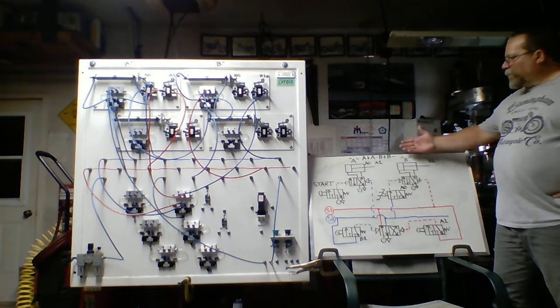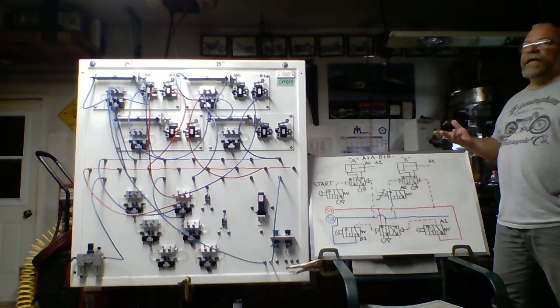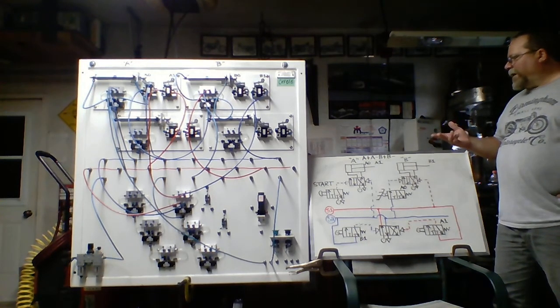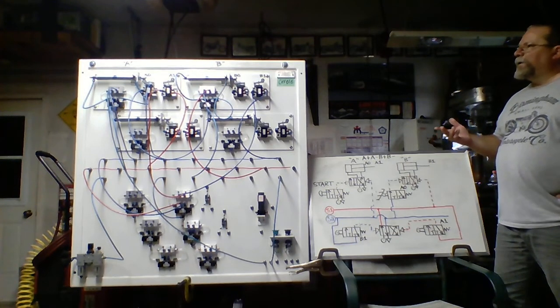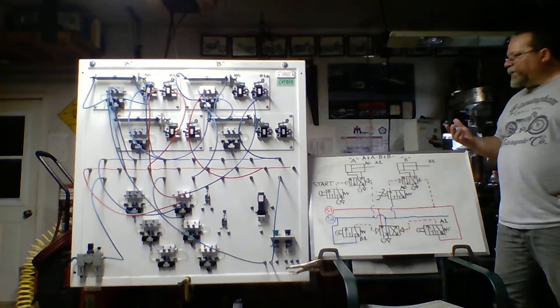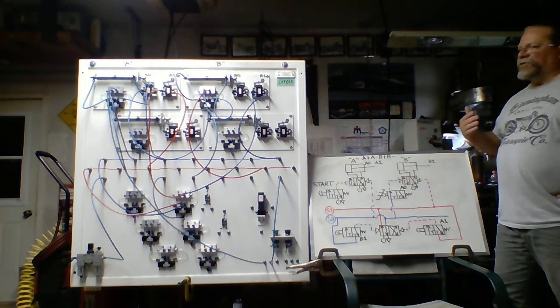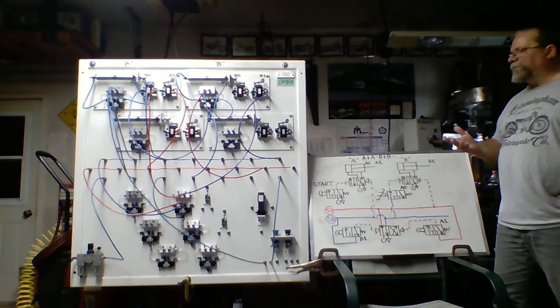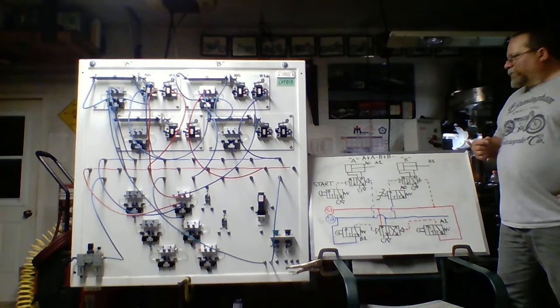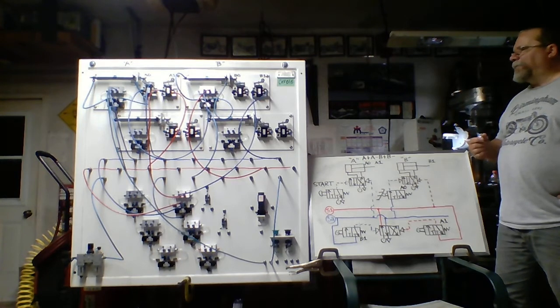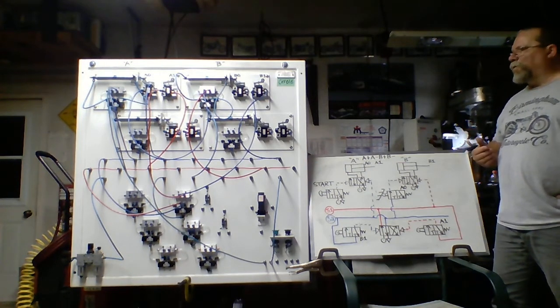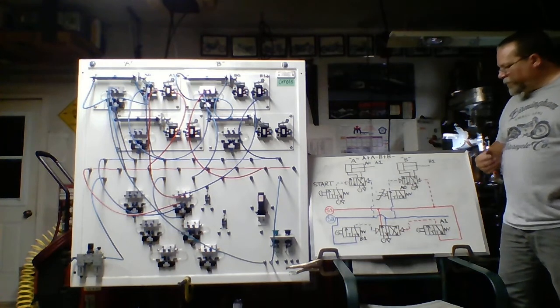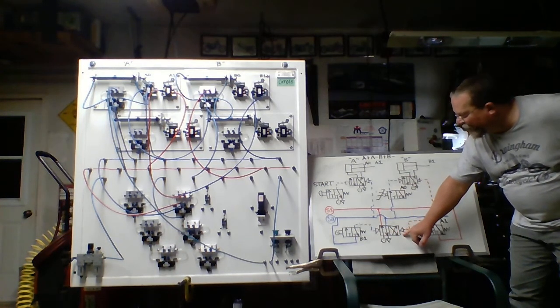So what this order of operations is suggesting is A will extend, then it will retract, then B will extend, and then it will retract. So using Cascade Circuits, the objective here is you're just utilizing air, no electrical, no other source or other means of shifting valves. So we have to use what we call a cascade valve, which is not a valve within itself, it's just one of the valves that are on the board. It could be a 5-2 or a 4-2. So looking down here at the bottom, we have a 4-2 valve.